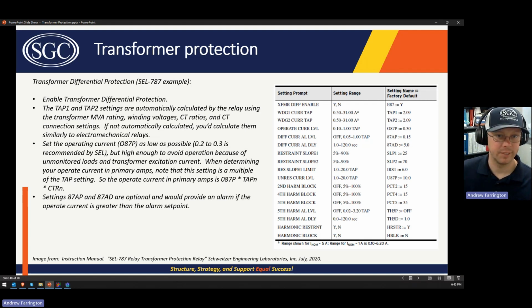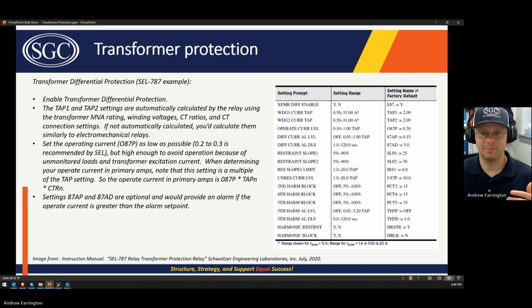But then you might have an out of section fault a year later, where now your operate current, because you've set the relay incorrectly, gets above that curve, and the transformer differential relay trips when it shouldn't have, when you should have had downstream protection operate. And it's happened. Luckily it hasn't happened to me very often, but it has happened to me, usually because the transformer connections were not per the drawings, which, not much you could do about that. But for the instance I'm thinking of, it was a mobile transformer, and so it was a temporary thing, and anyway, it happens.